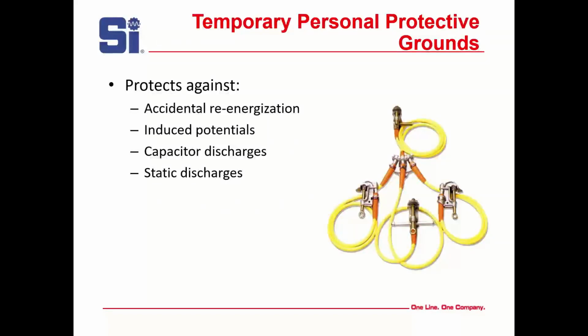So here's a shot of a well-constructed temporary personal protective grounding. And you'll notice you've got your ground connection and your three-phase connections. You've got your ferrules. You've got your connection points in the heads. All of these are rated to carry the maximum fault current, or they better be. So it protects against accidental re-energization, induced potentials, capacitor discharges, and static discharges.